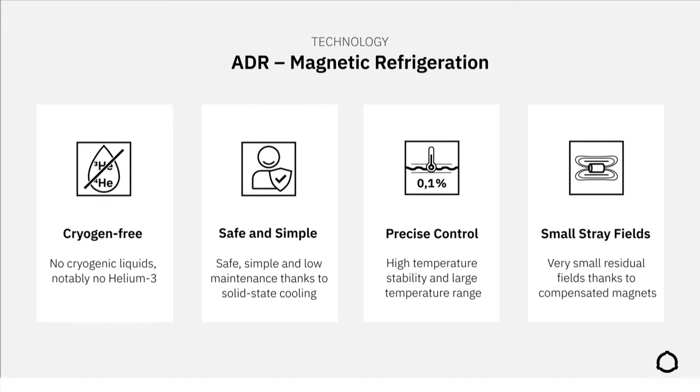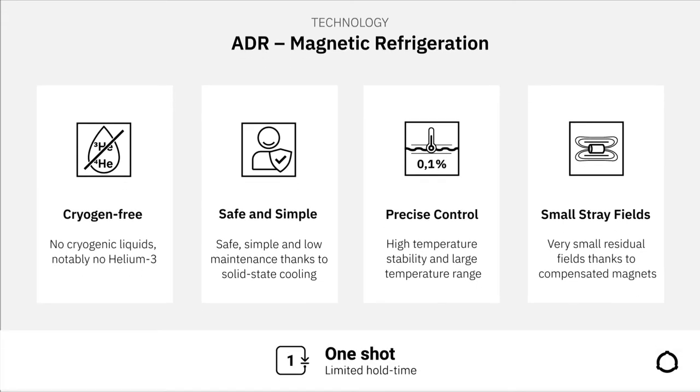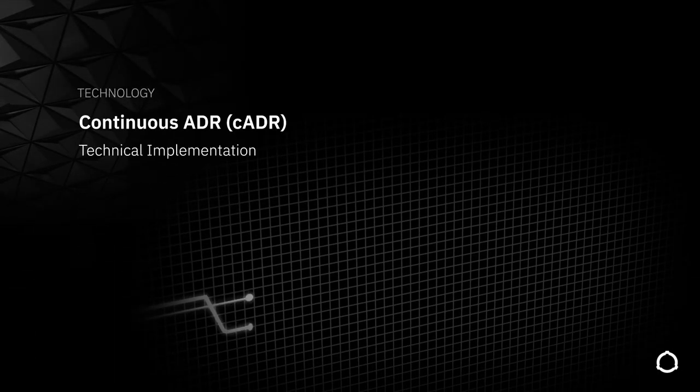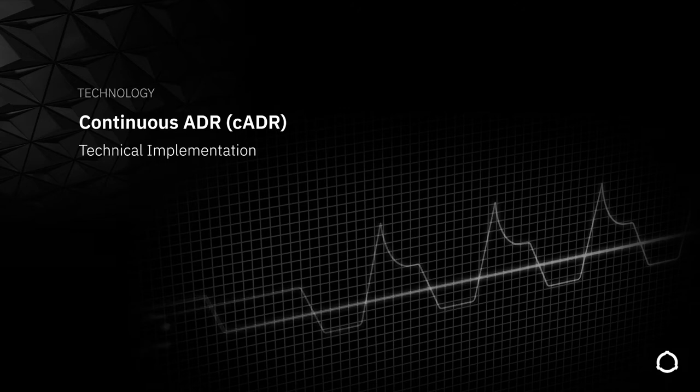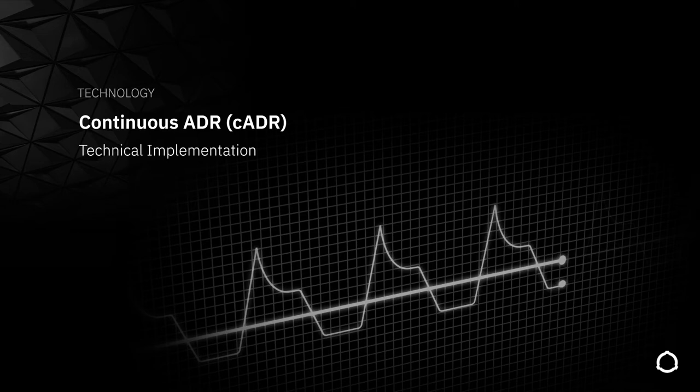The most obvious disadvantage of ADR is the limited hold time available for the experiment before the measurement needs to be paused to regenerate the cooling medium. Fortunately, for experiments and applications that really require permanent cooling, the limitation of one-shot ADR can be overcome. In fact, Qtra is the first supplier to implement both one-shot ADR and continuous ADR, or C-ADR for short.